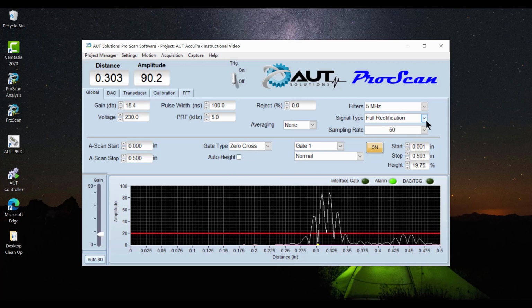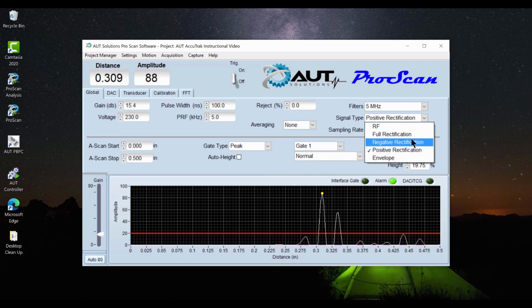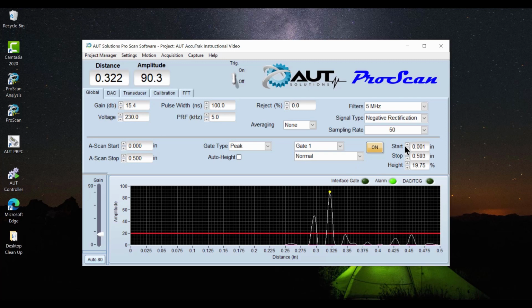Now if you had to use a different wave mode, say that you're required to run a negative rectified scan, you could simply come in, change this to first peak, and now you're getting your first negative peak through the gate. Same thing if you switch over to positive, you'll notice the phase shift and the time change as we are now recording the first positive peak through the gate. So if you wanted to get the maximum peak through the gate, you can change that there. Now you will notice it's reading the maximum peak here and not the first peak. The only problem with this is as the amplitude changes in the screen, you will switch signals, which could cause a deviation in a couple mils, which might be out of code pending your procedure.